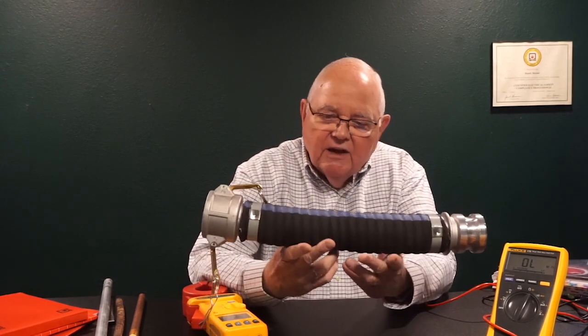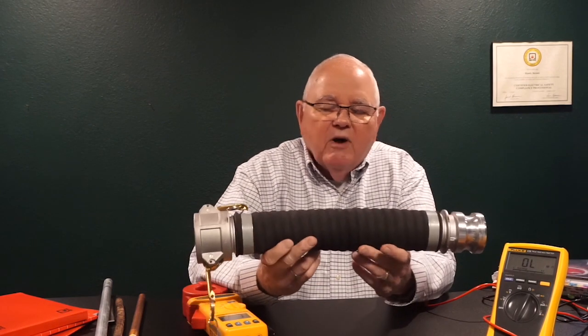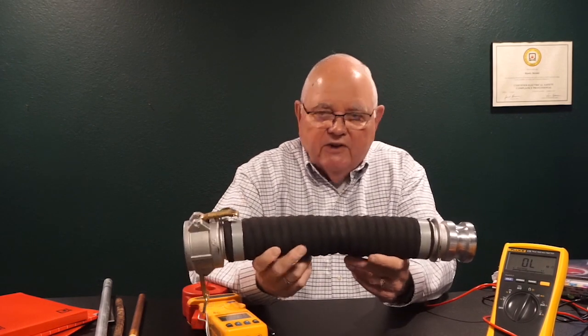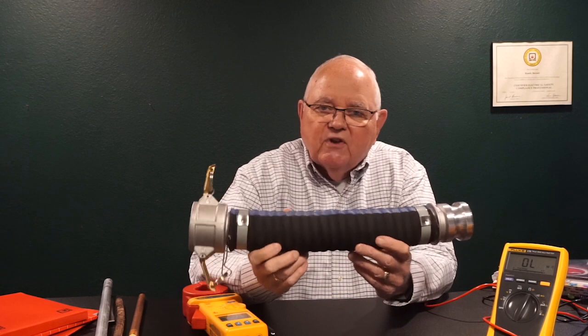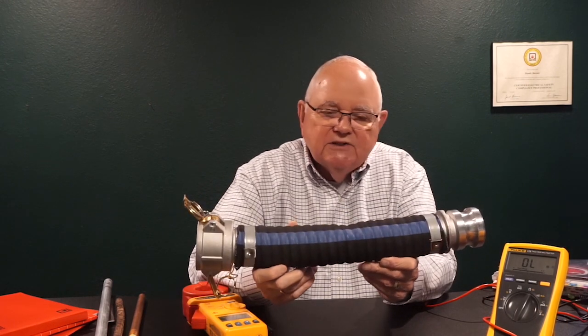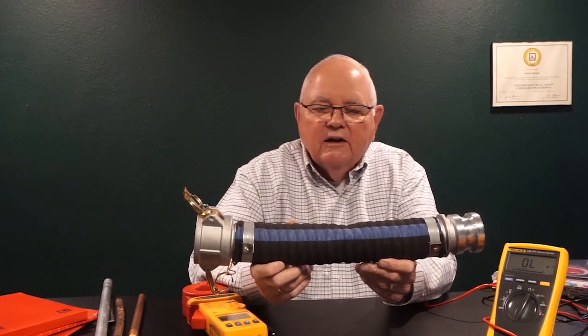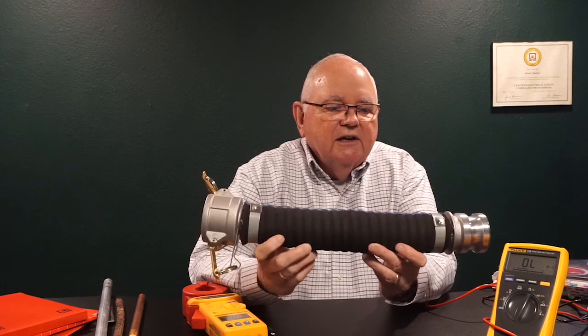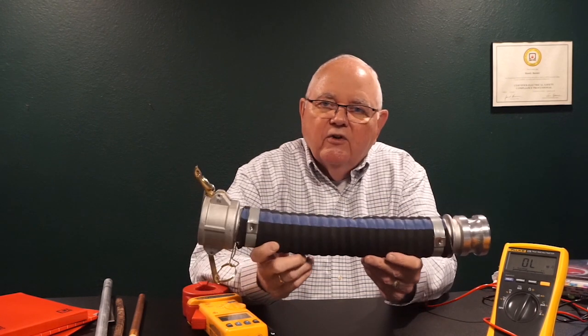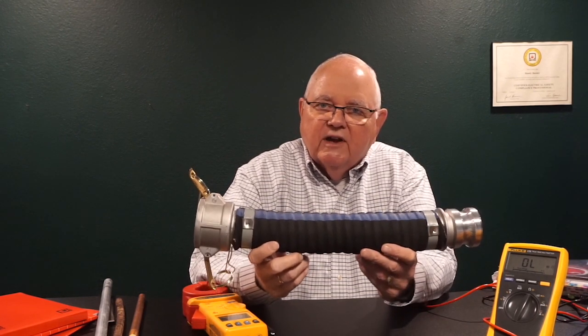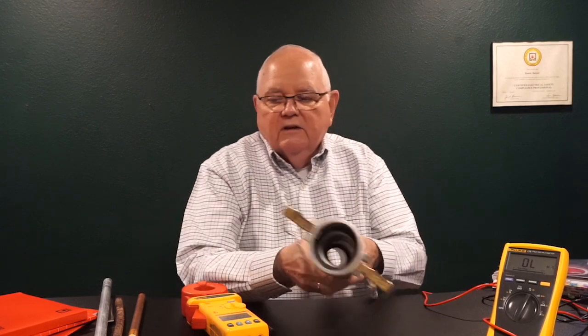They are conductive. From looking at the hose, there's no marking required to be on the hose to tell me it's conductive. There's a blue stripe here, that's for pressure ratings on the hose, but nothing required to tell me whether or not it is conductive. The only way you're going to know that is to put a meter on it and test it. Right? So that's kind of interesting.